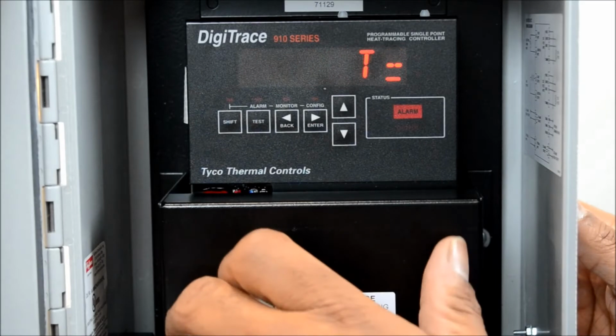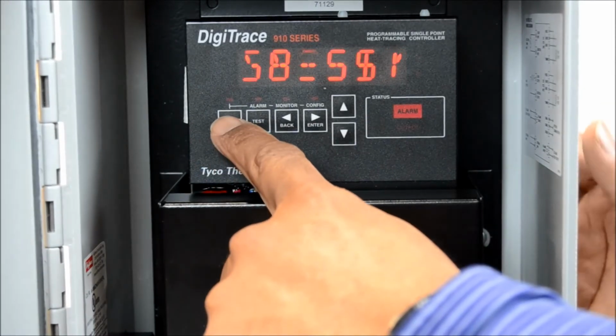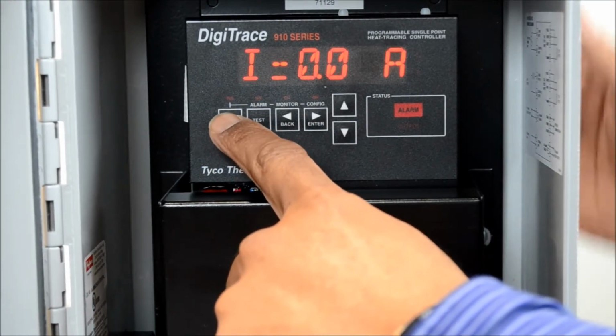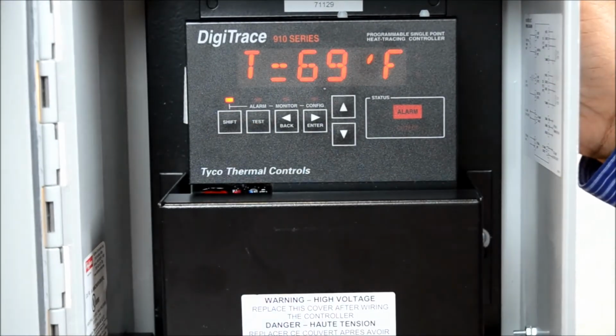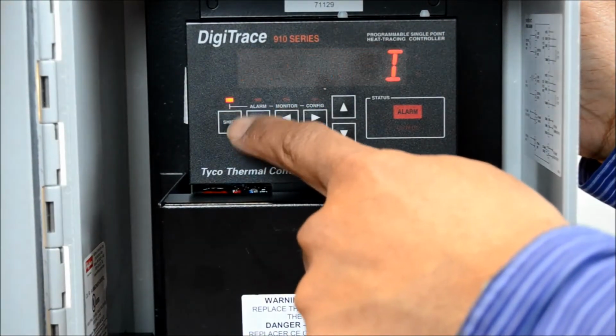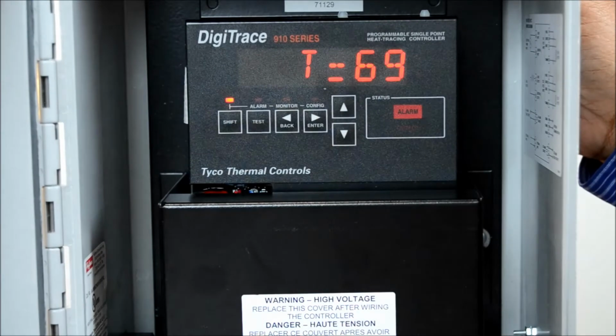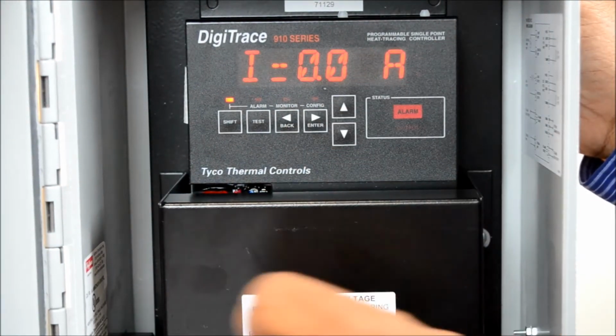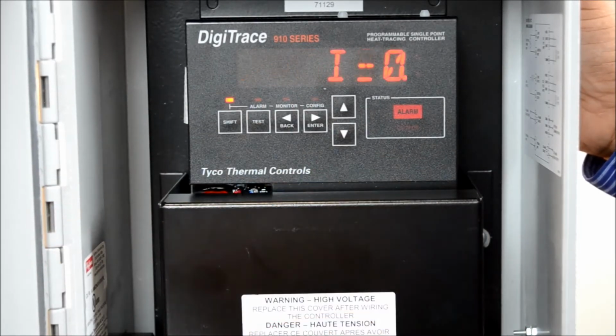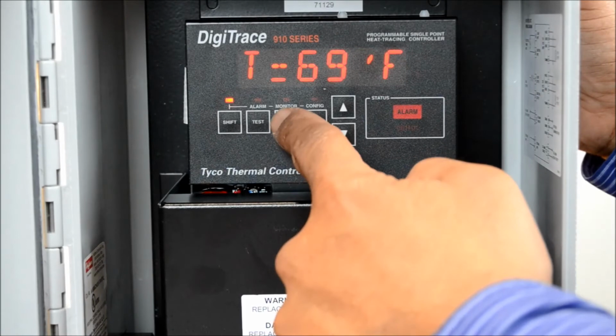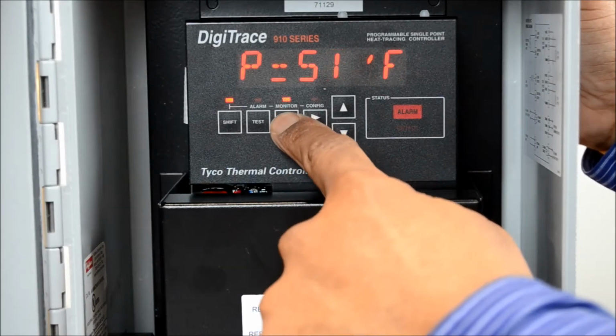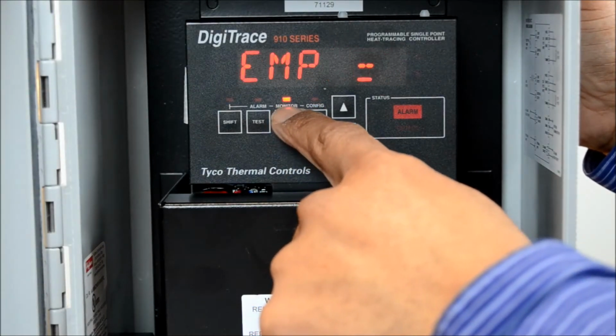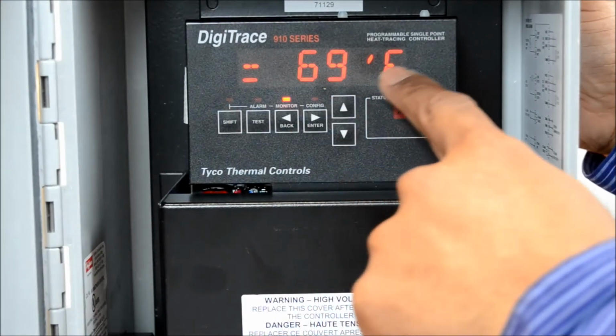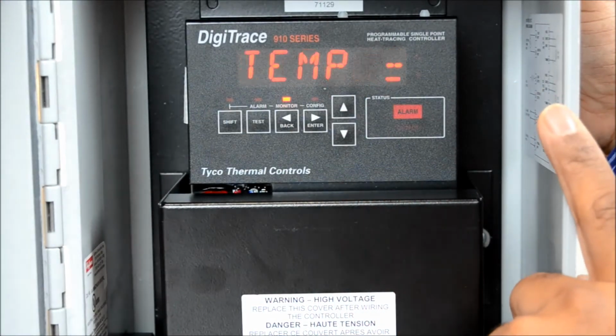Anytime you want to access the system, you always have to hit the shift button first. When you hit the shift button, that light will appear right above it. Now you can access the system. We're going to use the monitor because we talked about the monitor before, and I'll show you exactly what this device can monitor. So I'm going to go over to the monitor button here, and you can see the monitor button lights up here. Well, the first setting here is control temperature setting.